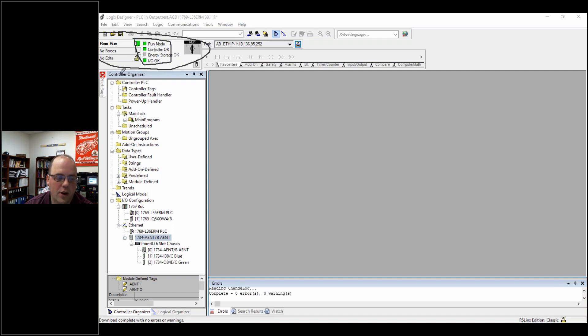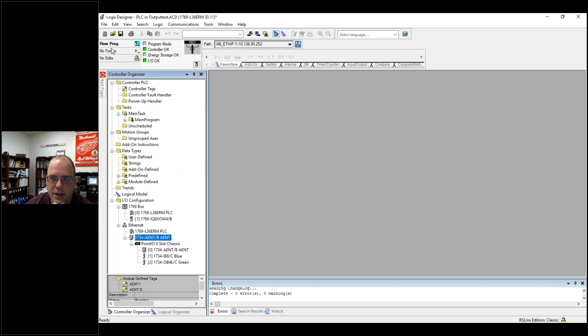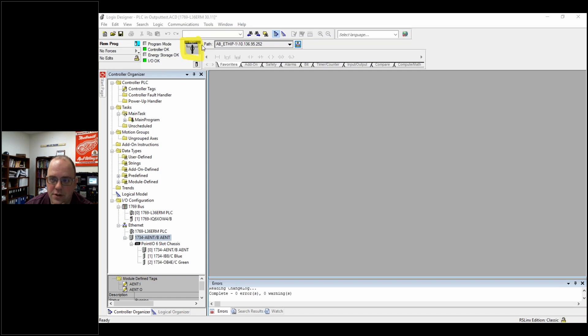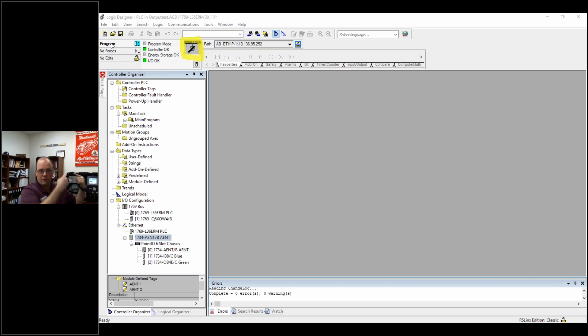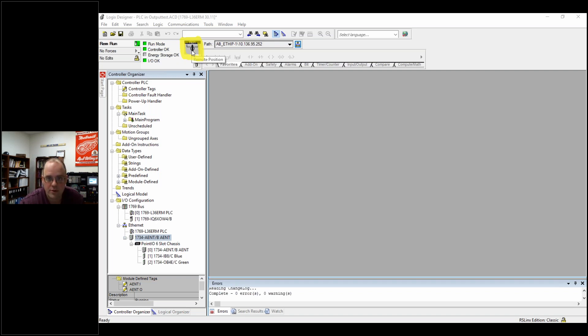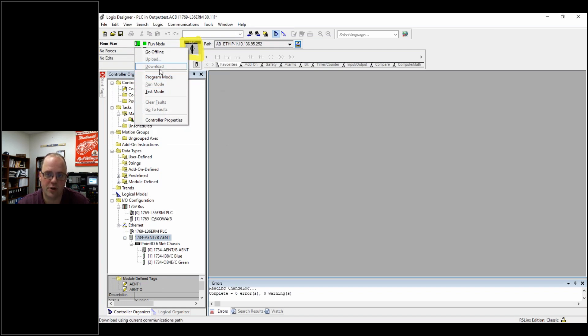A lot of times what will happen is when you first start your program, it'll be in remote program mode as evidenced by blue. Also take note of this right here, this box right here. This is what the switch says on the processor. If I move this to program mode, notice now two things. One, this switch is pointing to program, and you'll see this is just program. Outputs won't turn on. It's in program mode. So you need to go physically put the switch on the processor and either change it into remote or run. If I do it and run, it's going to say run, it's going to point here, but I won't be able to make any changes. So for our sake, I always put it remote so I can easily toggle between the two program and run mode.